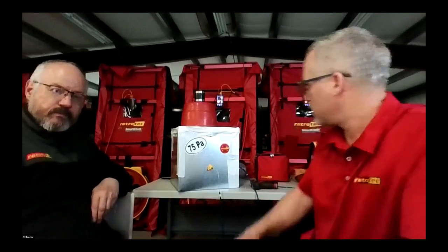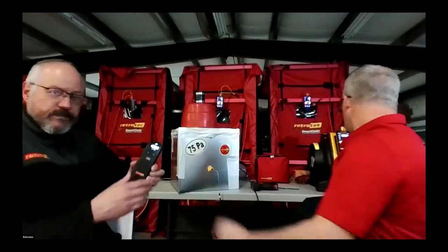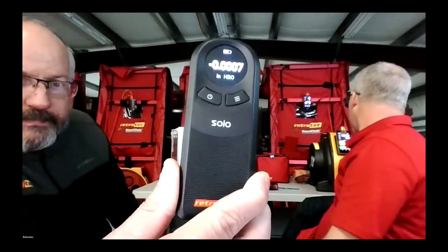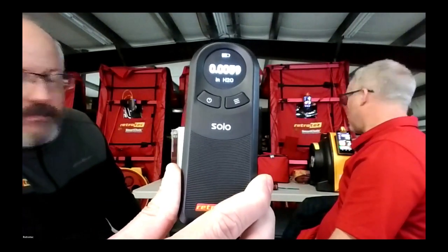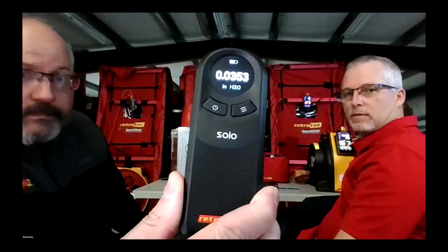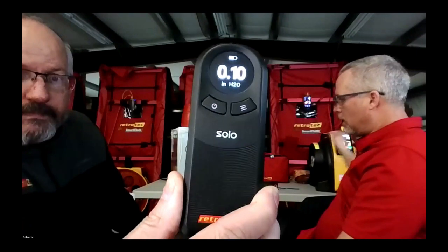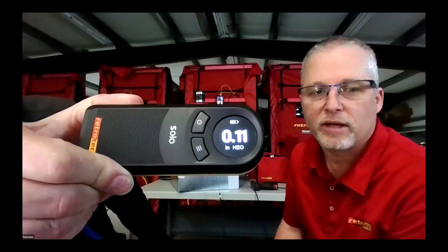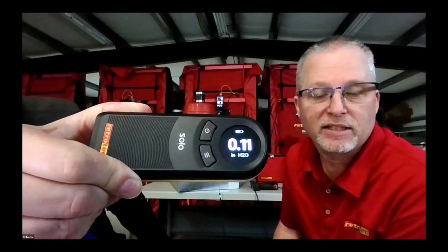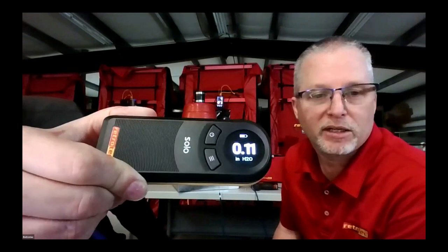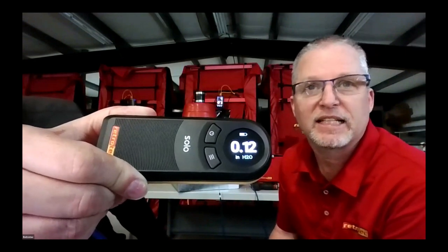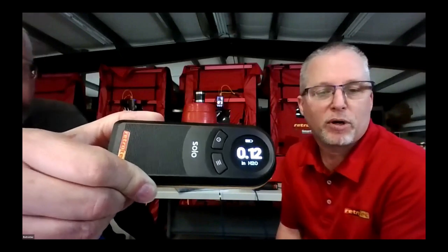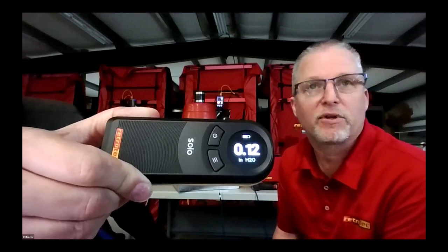We're going to demonstrate a little bit here just by turning the power on. With the mini probe inserted into the unit like that, you can get by any insulation that's inside there, and your airflow is going to be perpendicular to the end of the tube, so it's going to give you more consistent readings. It can also be used for laboratory work or clean rooms, just checking pressure differentials in there.